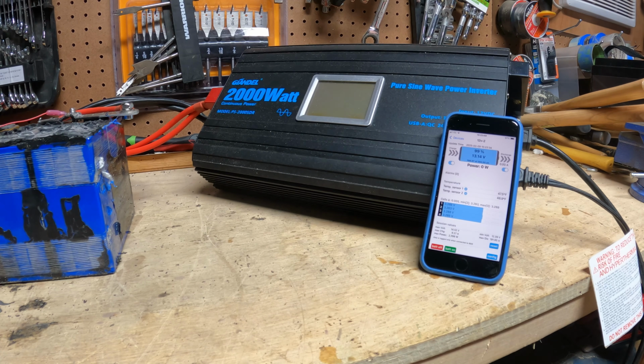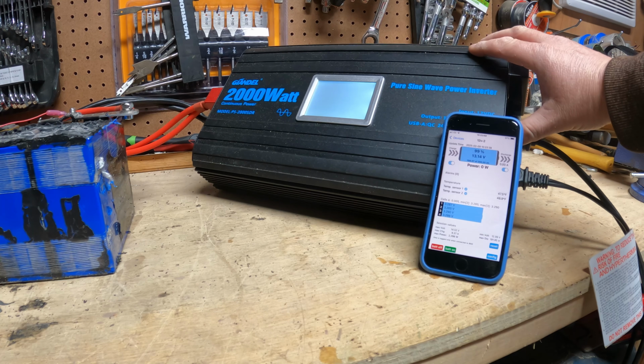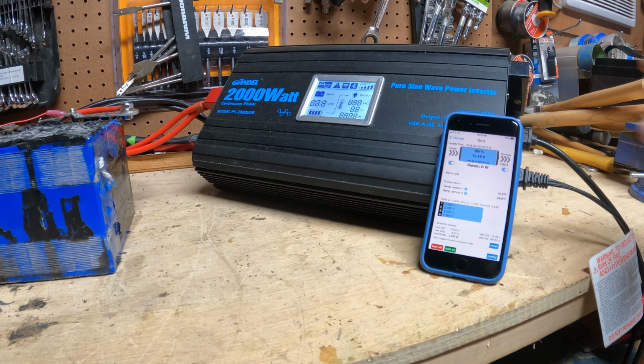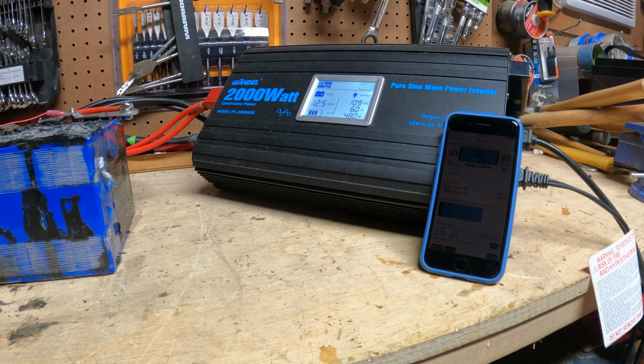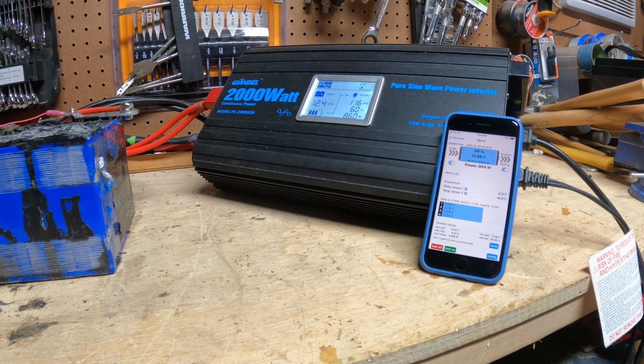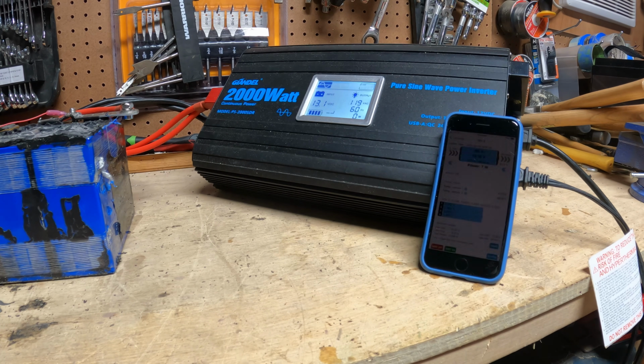There you go, now the battery is back to being turned on. We can turn the inverter back on, and then apply our loads again. This time I'm going to do a small load, and you can see the battery saying, hey, okay, you're doing 70 amps, I'm fine with this. So overcurrent protection is an absolutely critical part of the protection that the BMS offers.